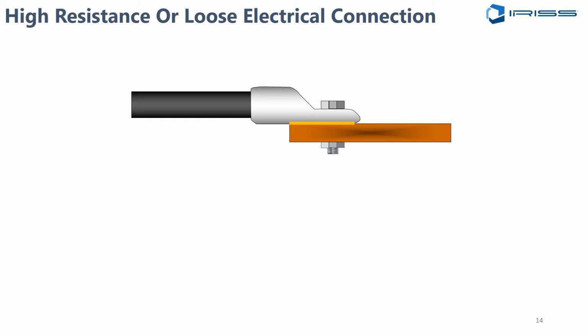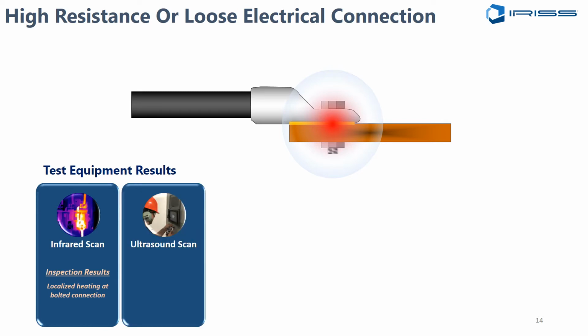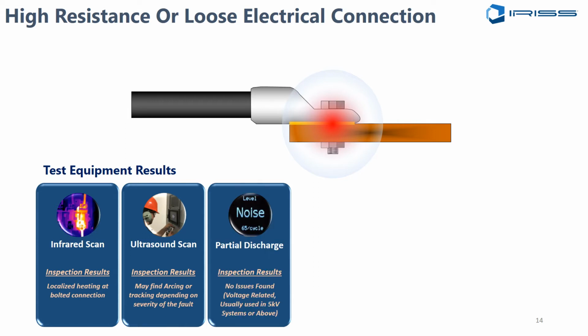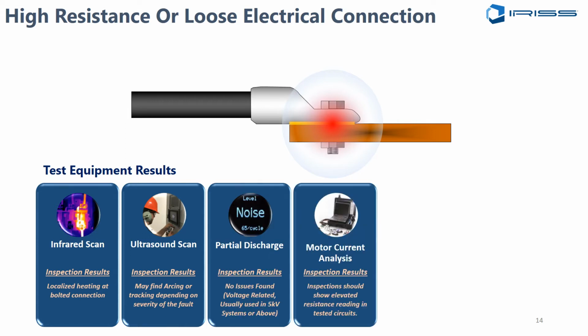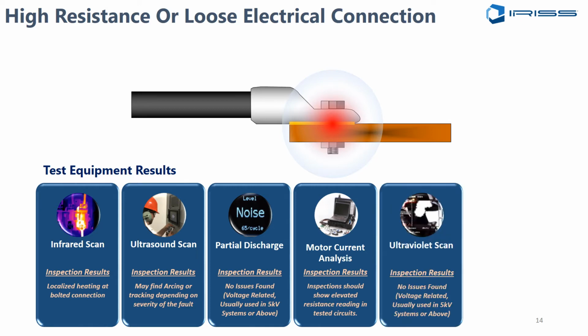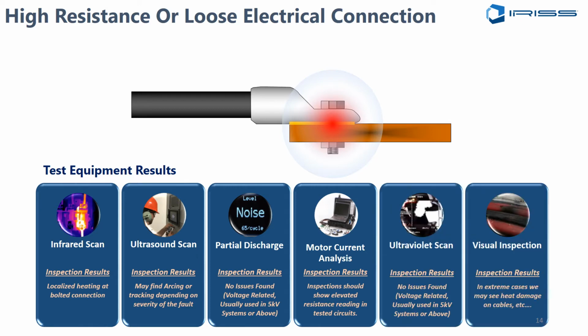Now, if you look at a high resistance or loose connection, here with the infrared, I'm going to see localized overheating. With the ultrasound, I may find arcing, tracking, or corrosion. Corrosion obviously depends on the voltage, but on medium to low voltage, we're going to find arcing or tracking in extreme cases. PD, possibly not, only if it's 5 kV or above. Motor current analysis, yes, I'm going to find this. Ultraviolet scan, again, only if 5 kV or above. And the visual inspection, again, in extreme cases where it's got so hot that it's visually discolored the circuit, we can see the evidence of that. So I can utilize these condition monitoring techniques to show me if I have a high resistance or loose connection.